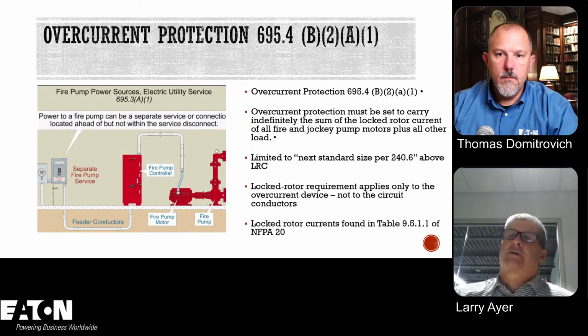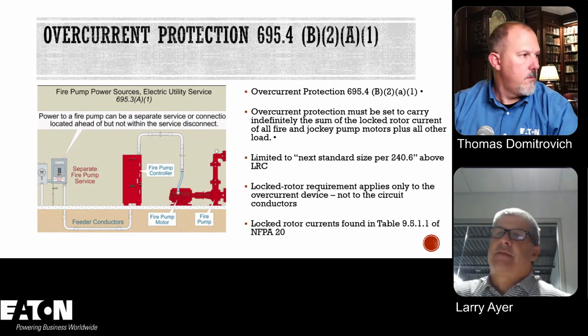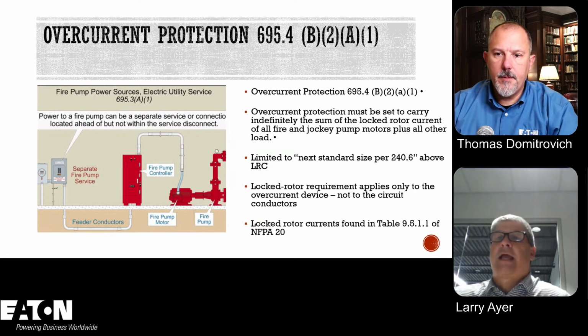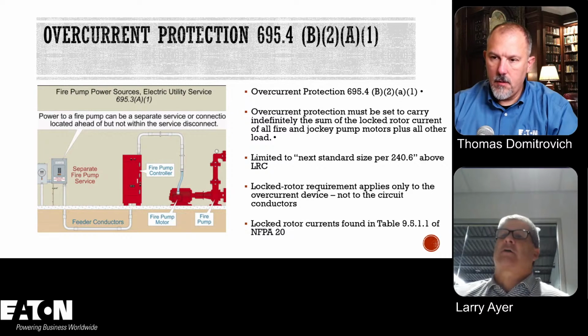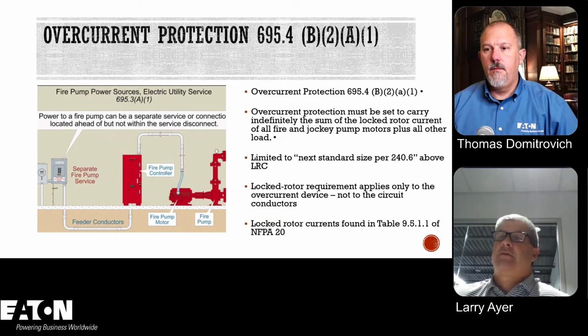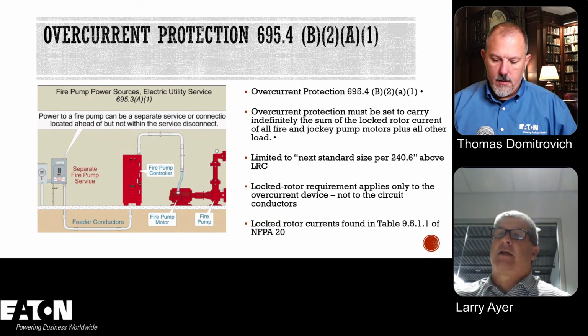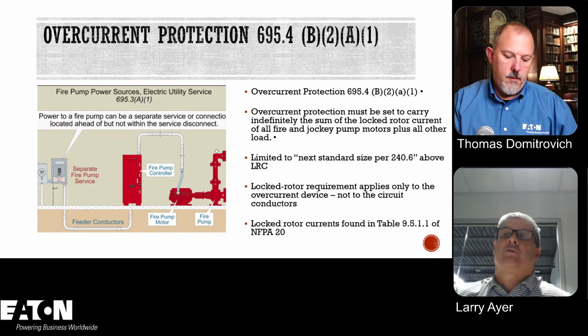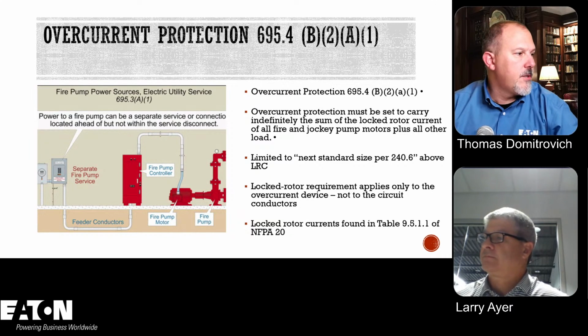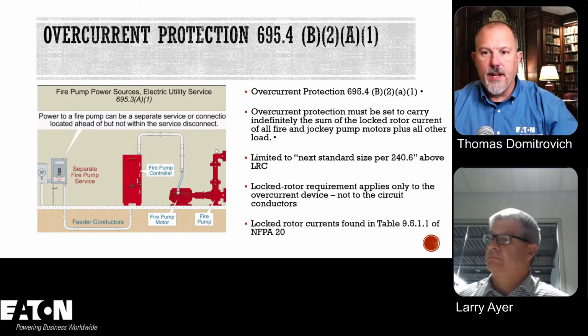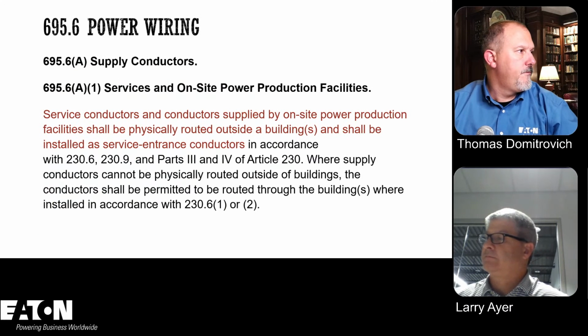So the circuit conductors are sized at 125% of the fire pump. Yep. And we mentioned there locked rotor currents found in Table 9.5.1.1 of NFPA 20, and that's not necessarily true. You could find those locked rotor currents in both NFPA 20 and in NFPA 70 Article 430. Right. For motors. Yep. So it's the same data from a motor perspective, but cool.